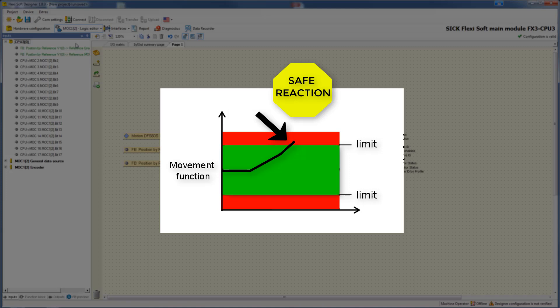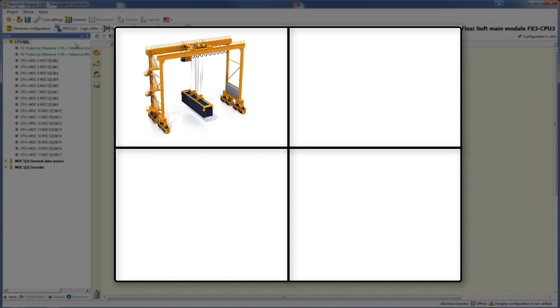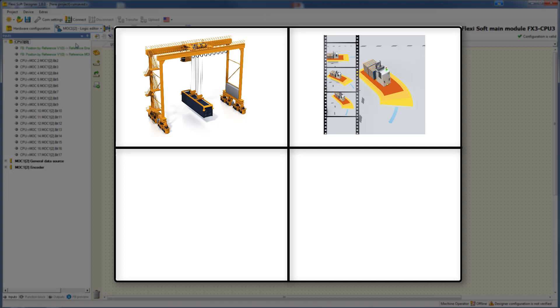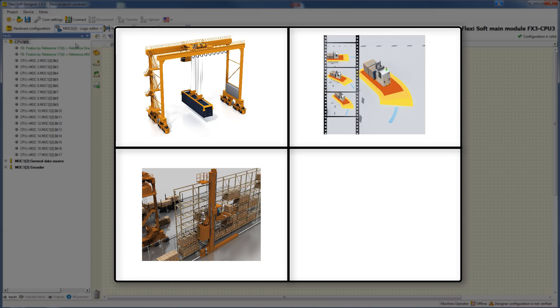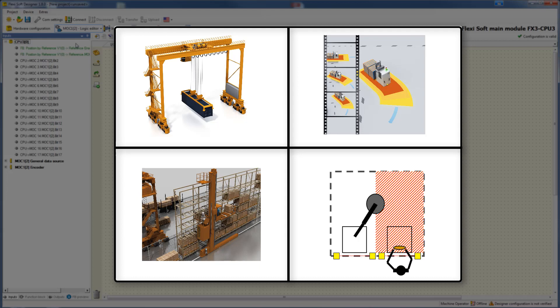This signal can be sent to a safety controller to react to the situation accordingly. Typical applications of the function safely limited position include indoor cranes where heavy loads have to be moved synchronously, AGVs where protective fields can be switched depending on steering angle, rack feeders to avoid hydraulic buffers, and robots where the position is safely monitored during material feeding from two areas.